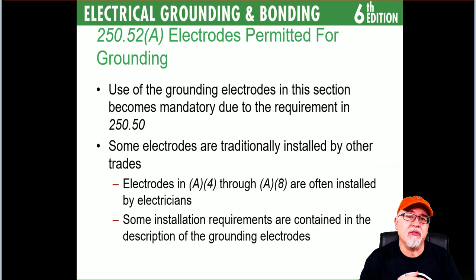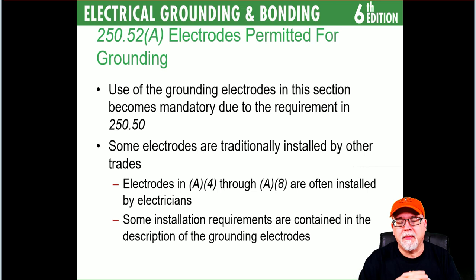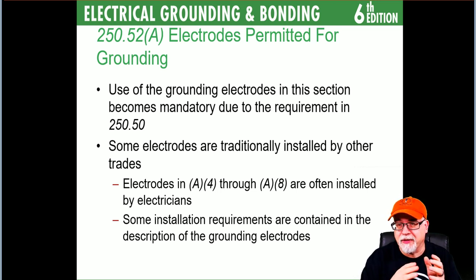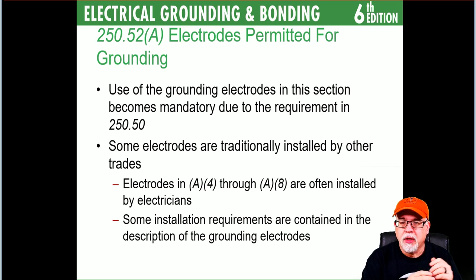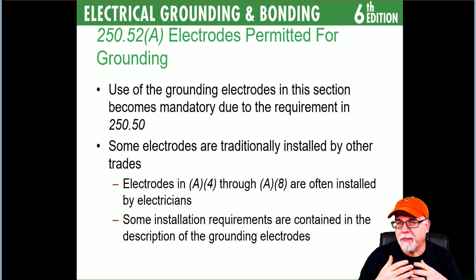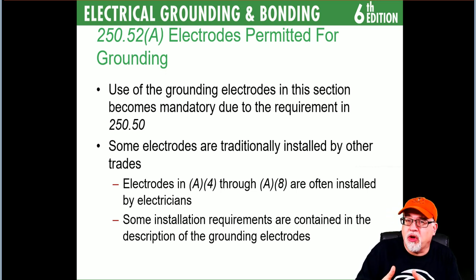If it's a concrete encased electrode or in-ground steel, you're essentially done — you don't have to do anything else. Sometimes plans will call for supplementing those, but you don't have to. Those three are usually inherent to construction. Whereas A4 through A8 are typically ones the electrician will have to install if the others aren't present.